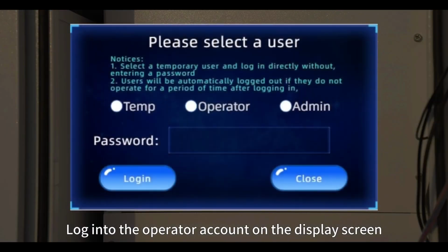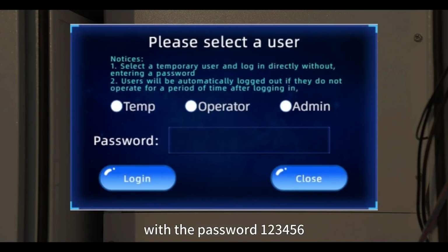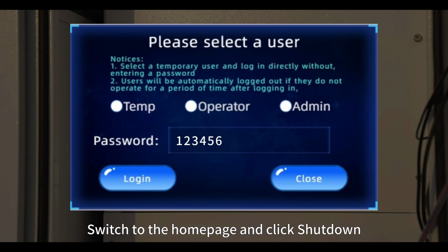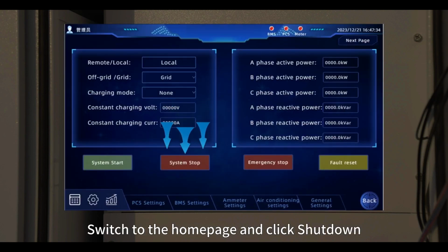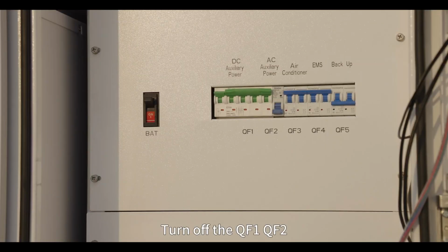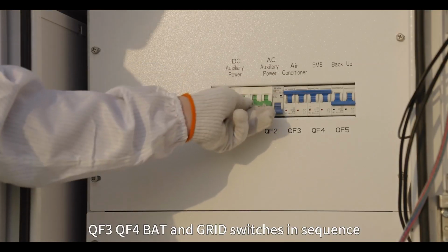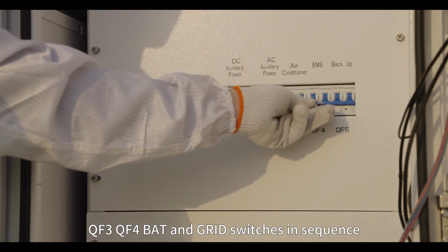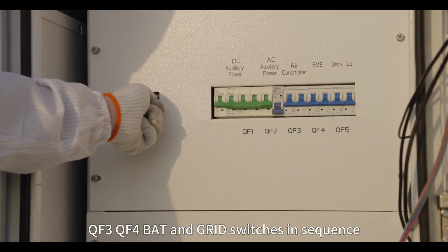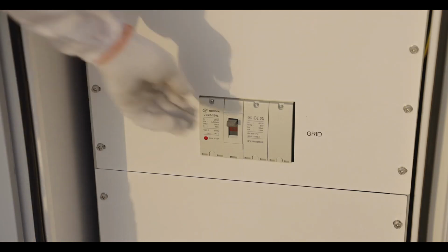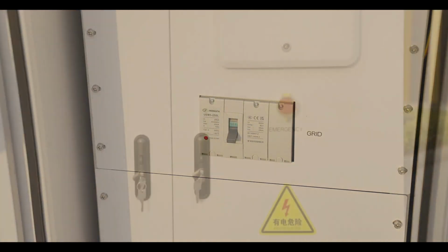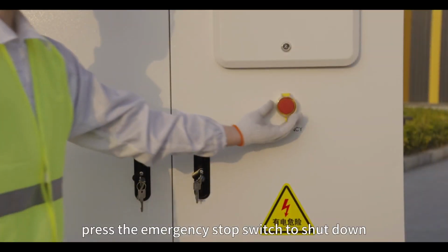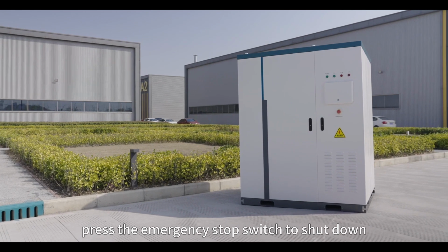Log into the operator account on the display screen with the password 123456. Switch to the home page and click Shutdown. Turn off the QF1, QF2, QF3, QF4, BAT, and grid switches in sequence. In case of an emergency, press the emergency stop switch to shut down power immediately.